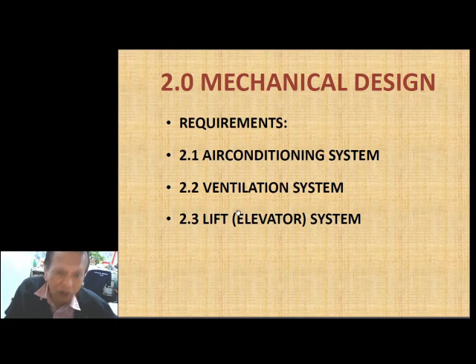Okay, so we proceed to the mechanical design. What's needed for mechanical - air conditioning loads, ventilation loads, elevator loads. This is for a mixed-use building. I use 15 square meters per 1 ton as my basis. Say I need a cooling capacity of 1 ton, that would be good for 15 square meters of area. Of course, if the room is only 12 square meters, it's still 1 ton. So 1 ton can be converted to horsepower by multiplying it by 1.2.